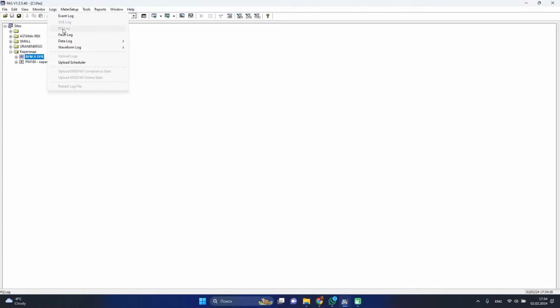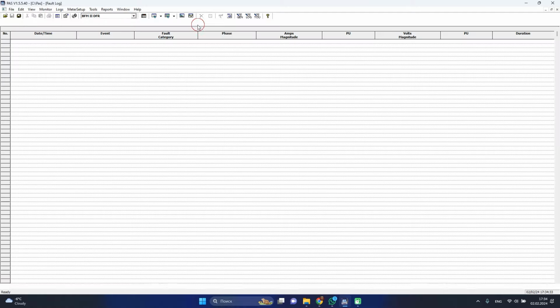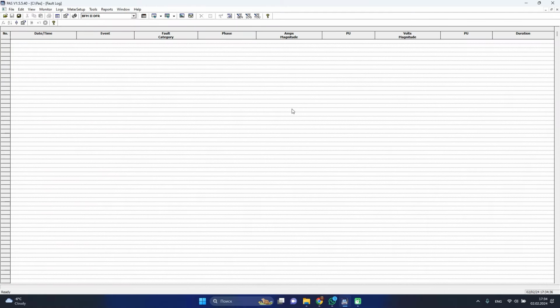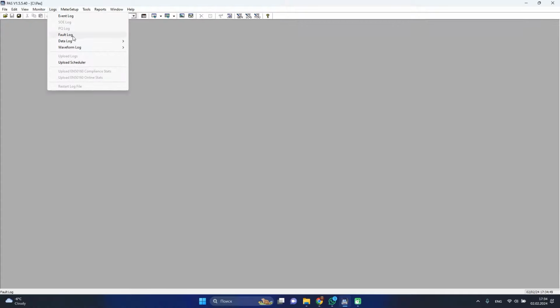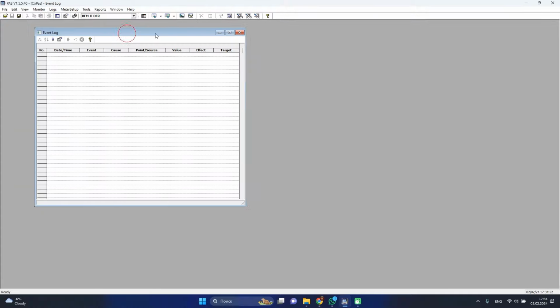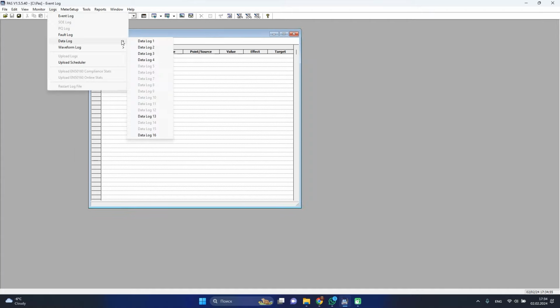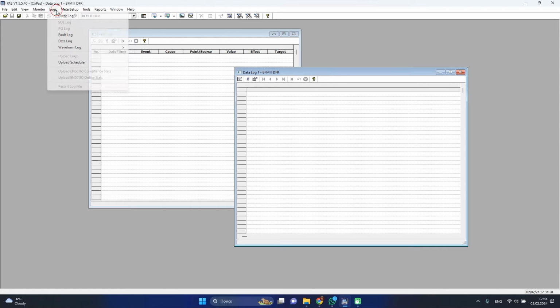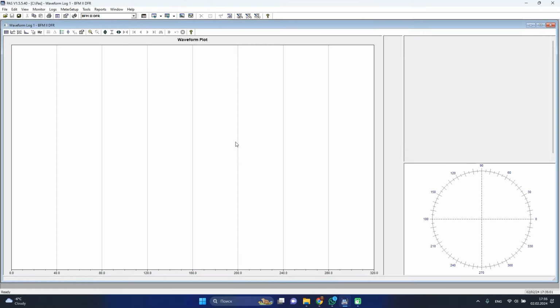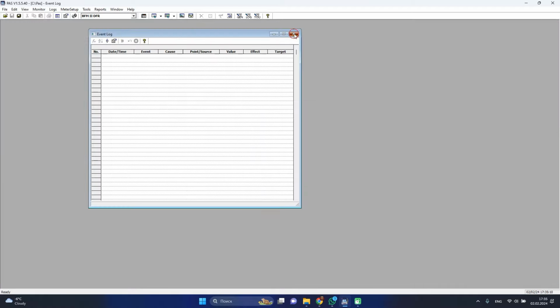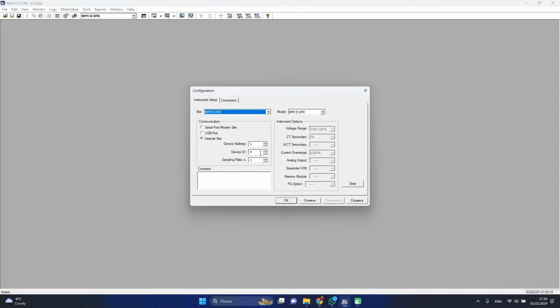So after that we can see the fault log. Here we will have information about the fault category, event, phase, and so on. And also we can see some information about the event log, about the events of the device, the data log for every submeter, and also we can see the waveform and phasor of the faults that we will have in the different feeders of the grid.